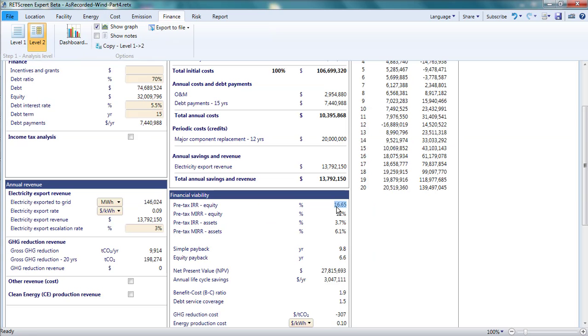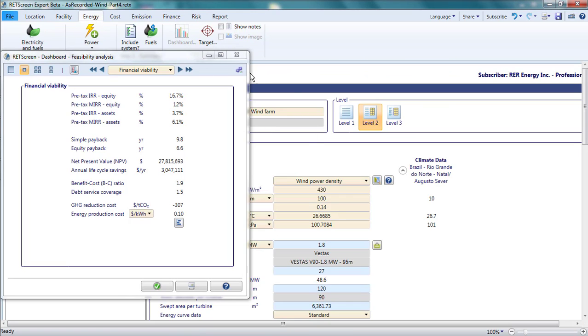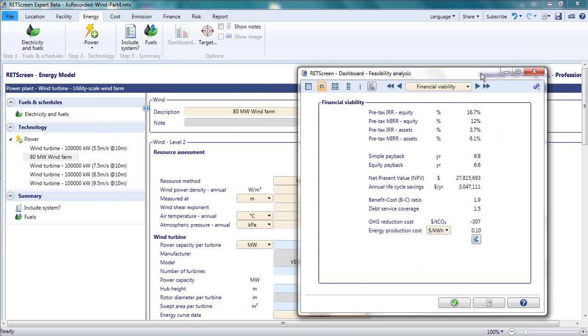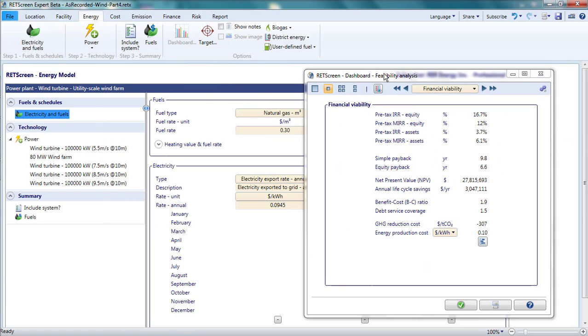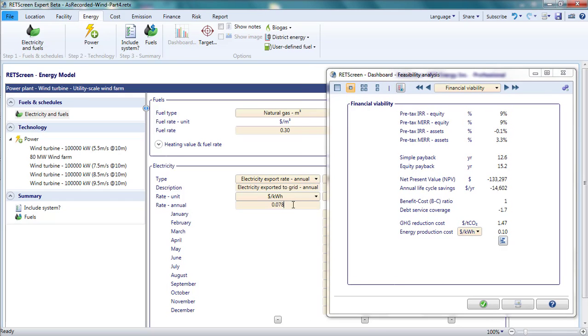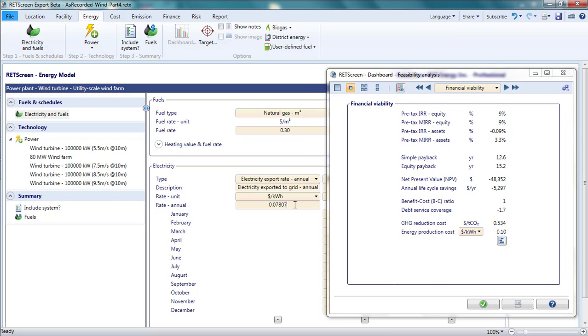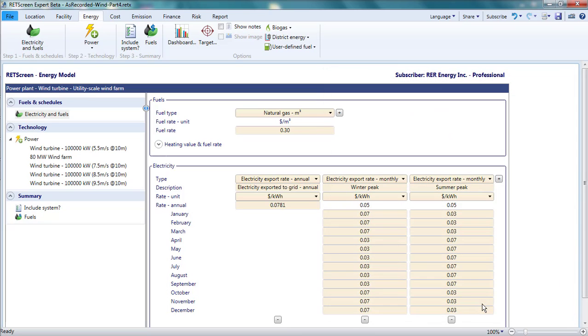Now our IRR is almost 17% if the price is 9.5 cents per kilowatt hour. Using the dashboard, I can show that the project would break even with the electricity price under 8 Canadian cents per kilowatt hour. Of course, taller towers cost more, and that was not reflected in the analysis.